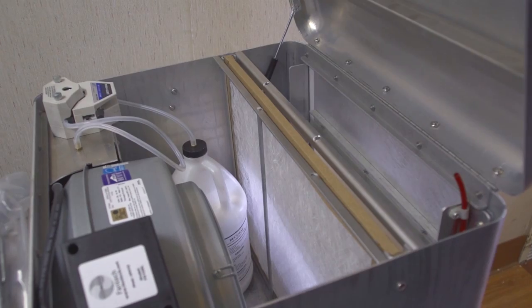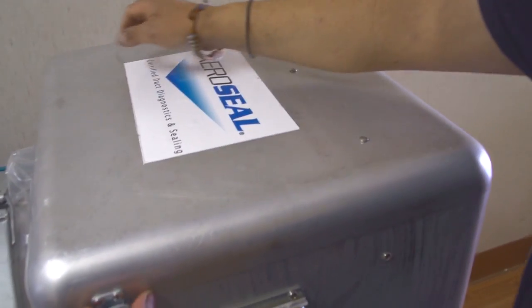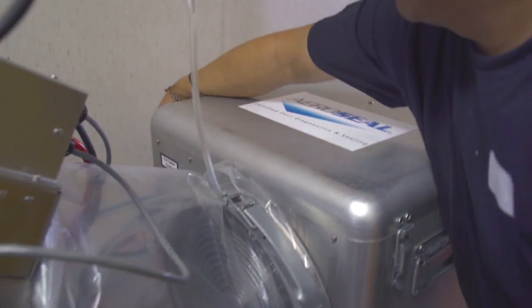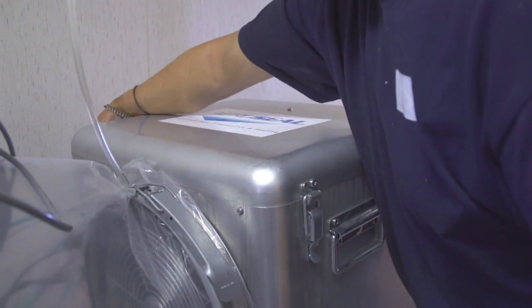The patented computer-controlled injection machine heats up adhesive particles suspended in liquid. As the particles are heated, they dry up and become suspended in air. The Aeroseal technology uses a fan to blow these small dry adhesive particles into the blocked duct system. The particles move through the ductwork at a constant rate of speed. As the particles approach a small hole, the air is forced into the small space as it tries to escape the ductwork. The particles stick to the side of the hole, and as more and more particles repeat this same action, the hole is soon filled.